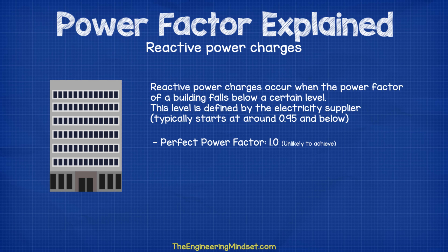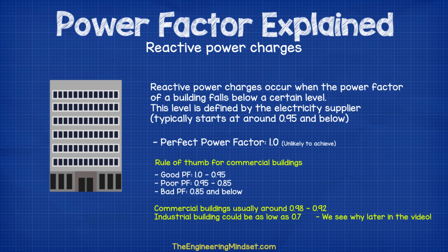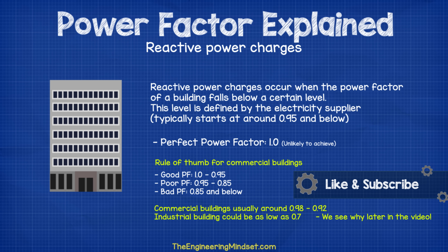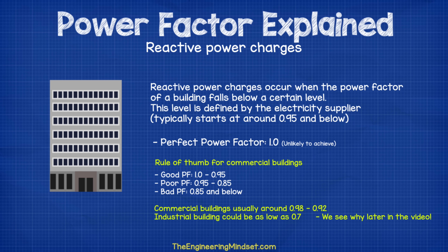In large commercial buildings, the overall power factor is likely to sit in the following categories: good power factor is generally between 1 and 0.95; poor power factor is anything from 0.95 down to 0.85; bad power factor is anything below 0.85. Commercial office buildings are usually somewhere between 0.98 and 0.92. Industrial buildings could be as low as 0.7.